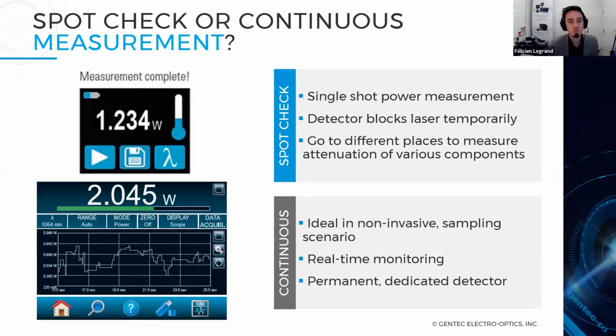First of all, the spot check is what we call a single shot power measurement, typically during 5 seconds. A measurement like we are offering with our Pronto series power meters, you just take a snapshot of the laser power. The detector will block the beam temporarily, but for a short period of time. Then you can go to different places along your beam path to measure the attenuation of various components and see how your laser beam behaves along this propagation axis.